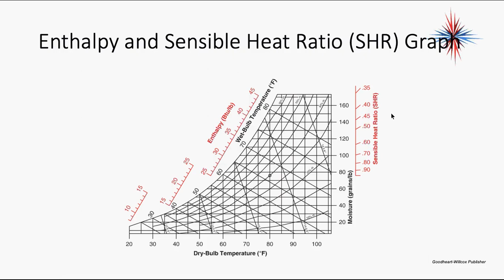To read a psychrometric chart, I need to know 2 points. If I know 2 numbers, 2 lines that cross, I can come up with every other value on this chart. So if I know relative humidity and dry bulb temperature, I can tell you what the wet bulb is. I can tell you what the enthalpy is. Most often, the 2 numbers we use are the wet bulb and dry bulb temperatures. Those are the easiest to get, and it's the most accurate. So once you know any 2 numbers, you can find the other values.